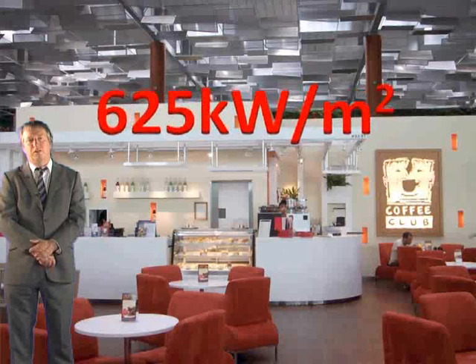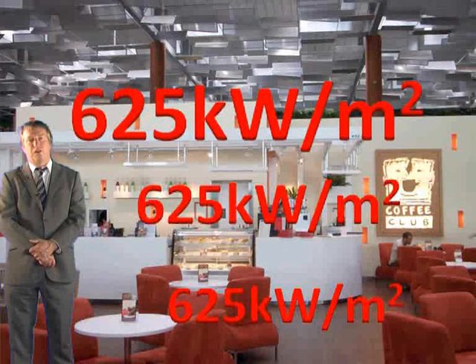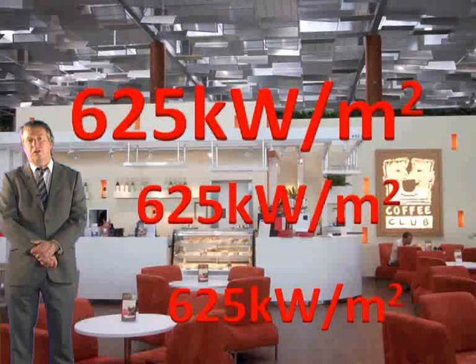A common value that is used is 625 kilowatts per square metre, and this is often used for sprinklered fires involving unknown or unspecified contents. 625 kilowatts per square metre is used as it is considered to be conservatively high.